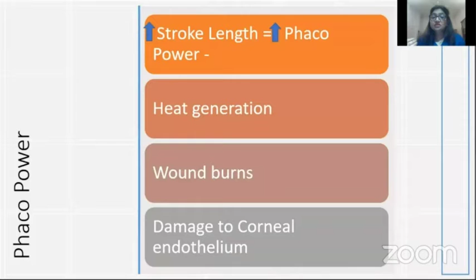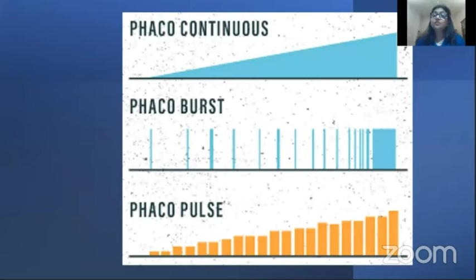So increase in the stroke length is basically increased phaco power, which can generate heat, cause wound burns, and damage to the corneal endothelium. You can modulate the power with the help of phaco pulses or burst modes, by which harder cataracts can be emulsified with less amount of phaco power.